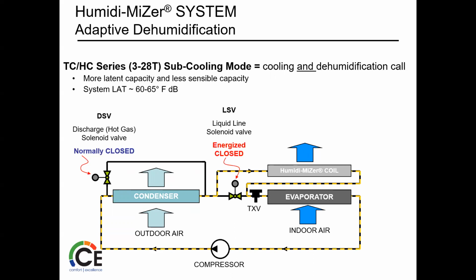So warm liquid flows from the condenser through the Humidi-MiZer or the reheat coil, which reheats the indoor air to a cool 60 to 65 Fahrenheit. This subcools the refrigerant to a cooler liquid. The cooler liquid flows through the TXV and changes to a cold liquid. Cold liquid flows into the evaporator, where the indoor air is cooled to a lower than normal temperature and evaporates the refrigerant to cool gas.